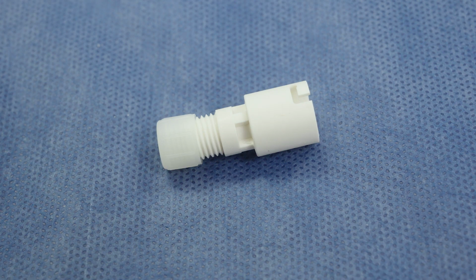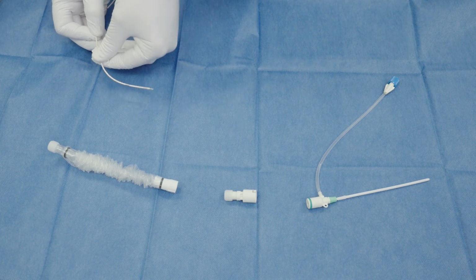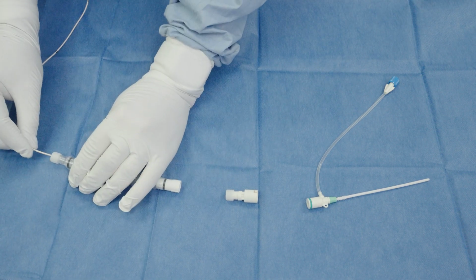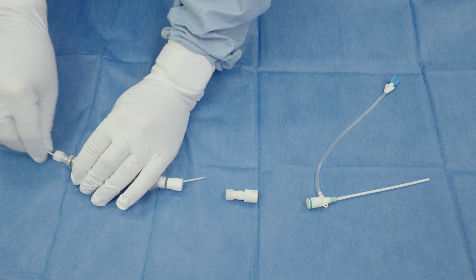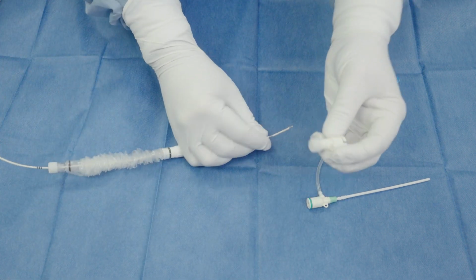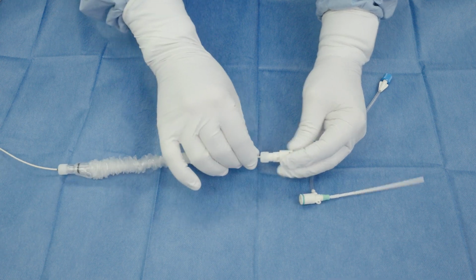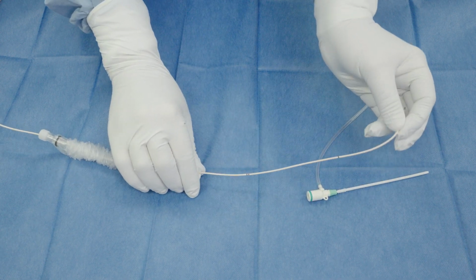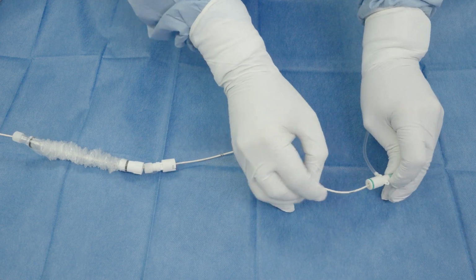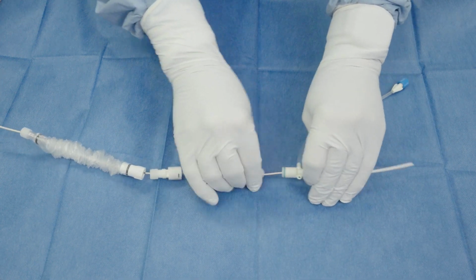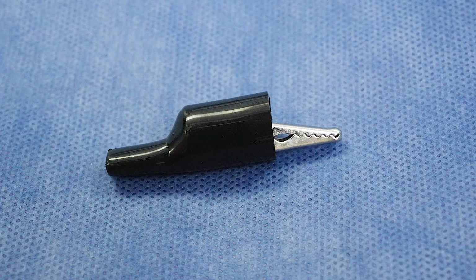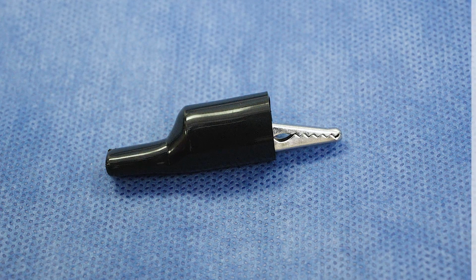The catheter kit includes 2 Tuohy-Borst adapters designed to hold the catheter in place after insertion and after being placed into position. Assembly of the catheter prior to insertion includes positioning the sterile sleeve with the Tuohy-Borst end going on first and ending up most distal to the insertion site. After the sterile repositioning sleeve, a single Tuohy-Borst is placed on next with a sheath locking mechanism nearest the sheath hub. To aid in placement, the included alligator clip may be used to attach the distal lead of the pacing catheter to the V-lead of an isolated ECG.